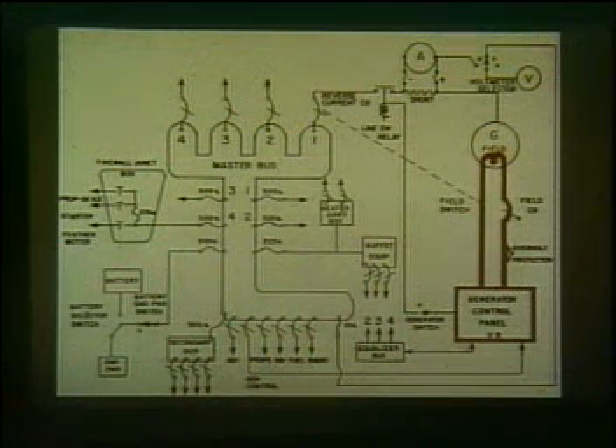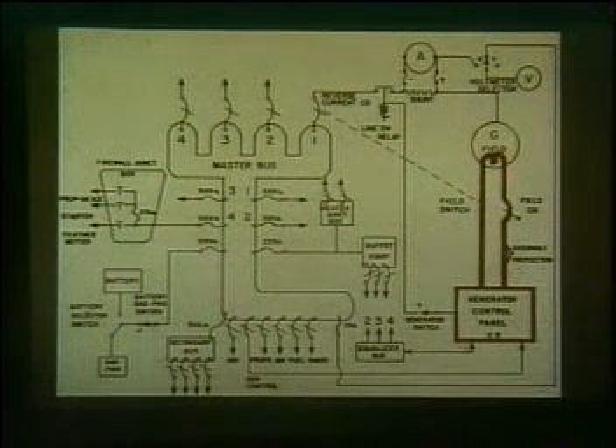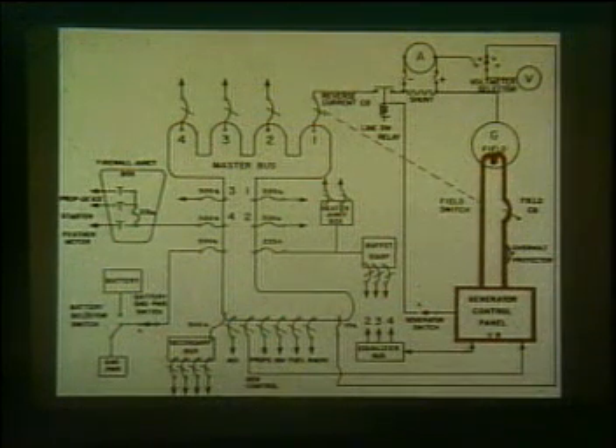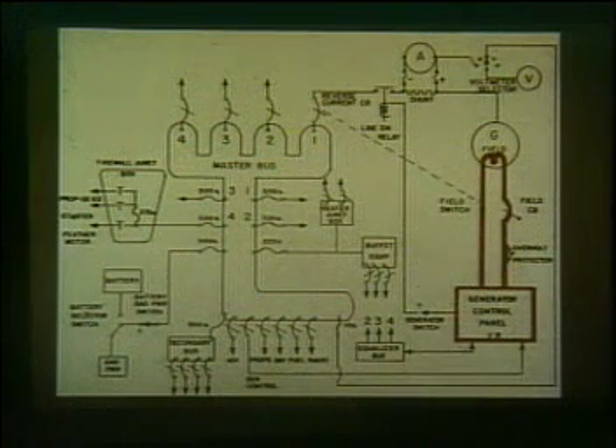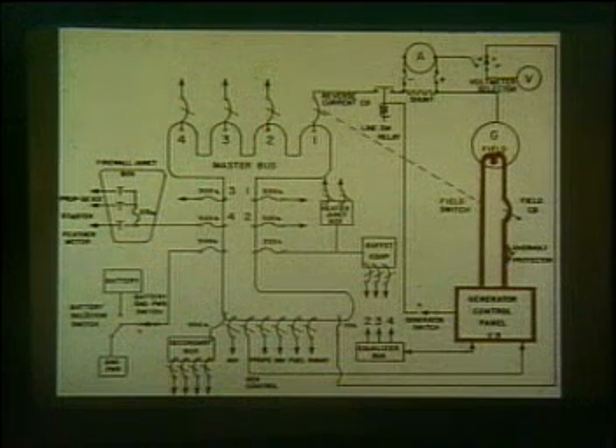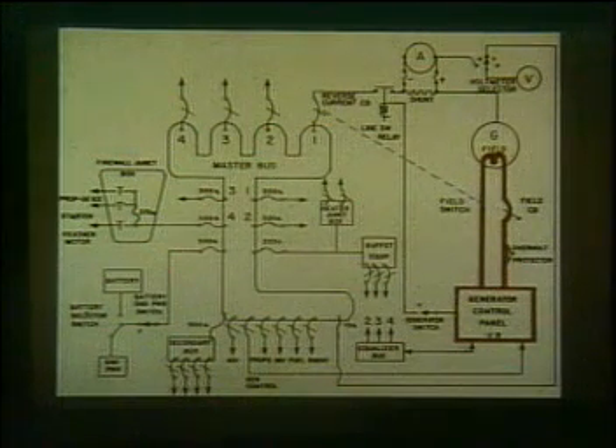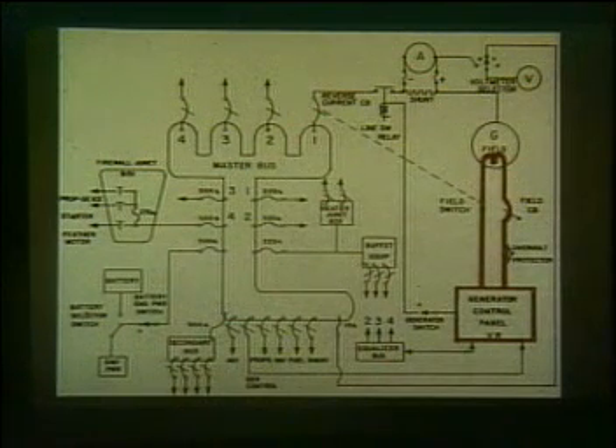A carbon pile voltage regulator on the generator control panel will respond to the generator output voltage and will vary the amount of current through the generator field to maintain a constant voltage output throughout a wide operating range of generator speeds. This voltage is normally set at 27.5 volts.